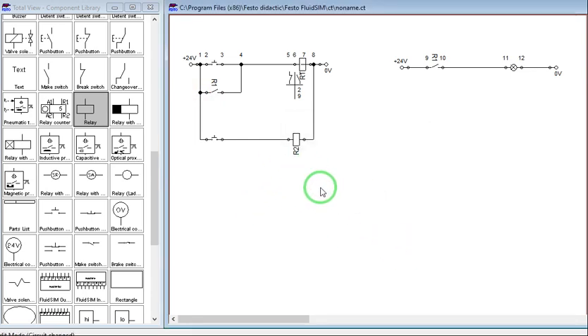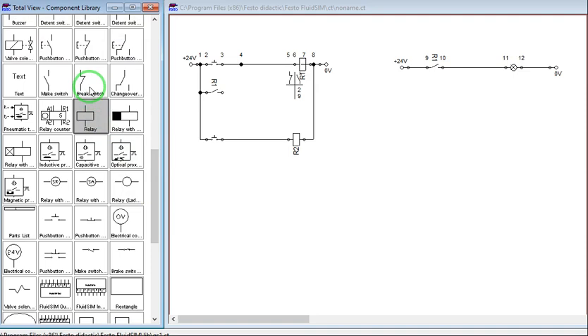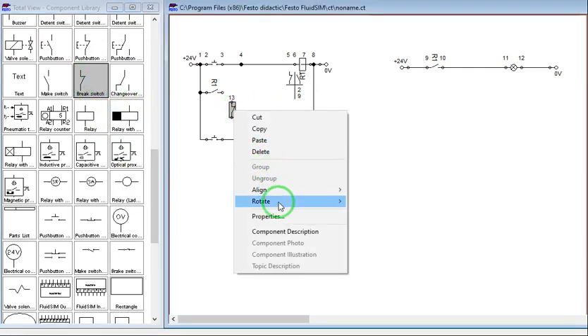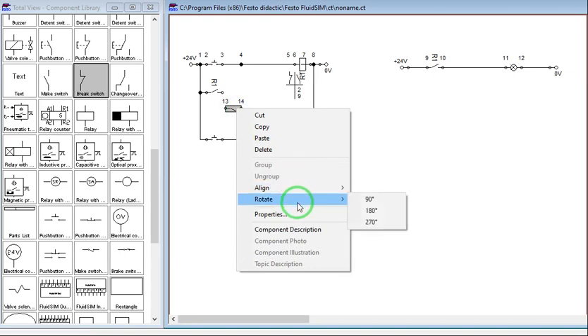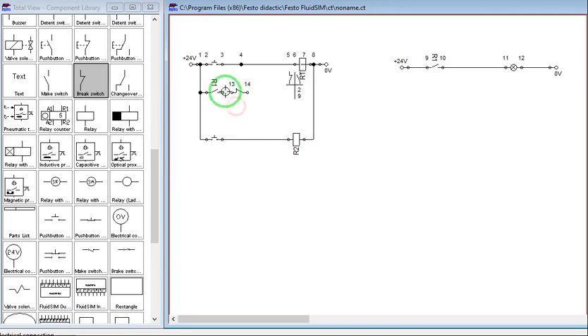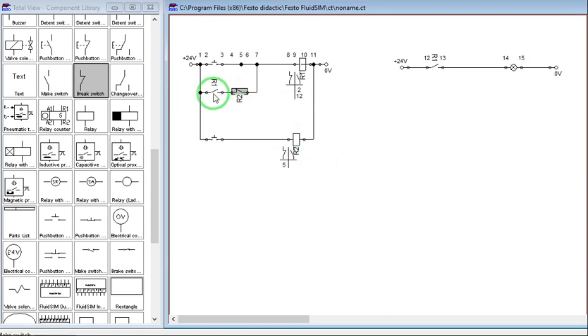Since we are going to make a set priority latching circuit, let us disconnect this one and add a normally closed contact. This is the normally closed contact — let us rotate this. This normally closed contact of R2 will be connected in series with the normally open contact of R1. So these two auxiliary contacts are for R1, and this one auxiliary contact is for R2 — but this one is normally closed.